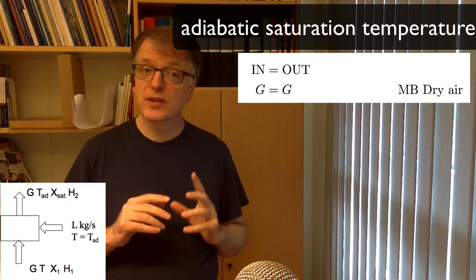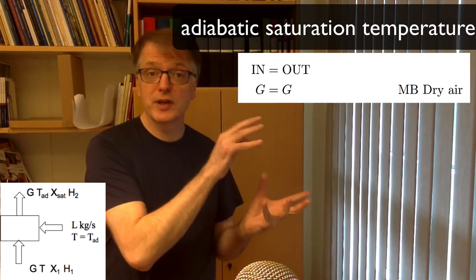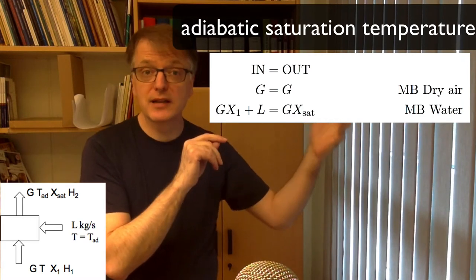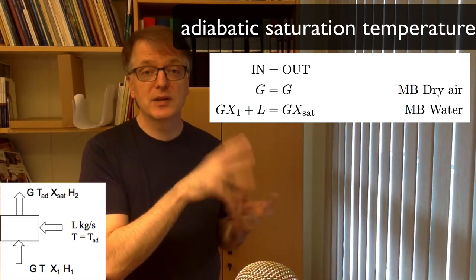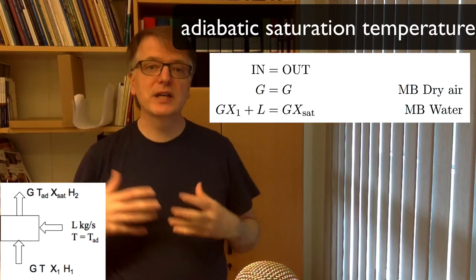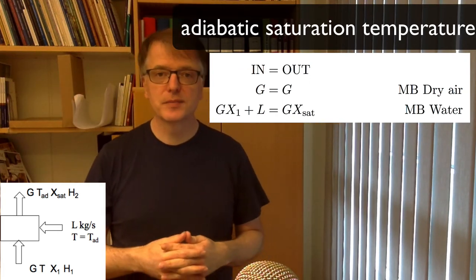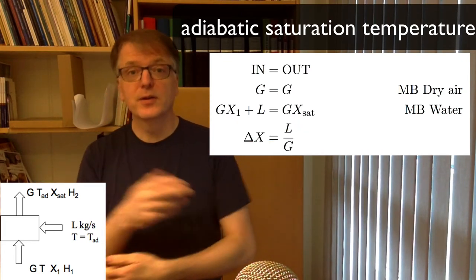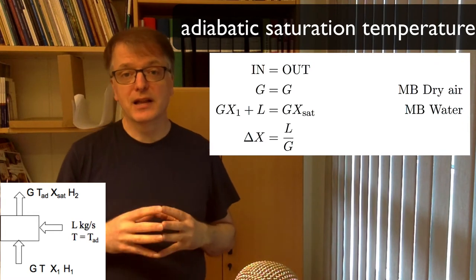But for water something happens. You have the water content of air, G times X coming in, but you also have the liquid coming in and we'll call that L. So G times X plus L equals G times X at the saturation point. So that we can express a difference in X in terms of G and L.